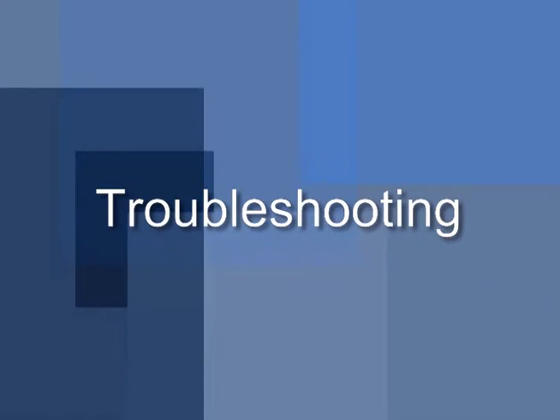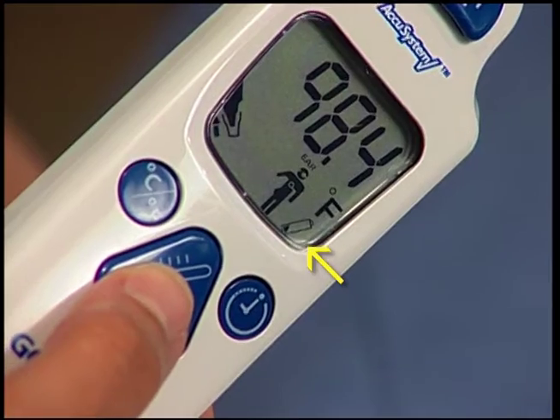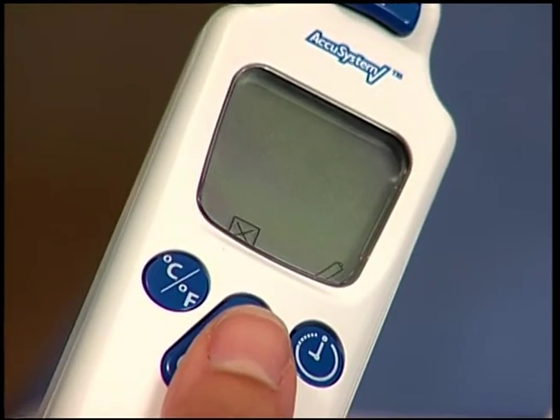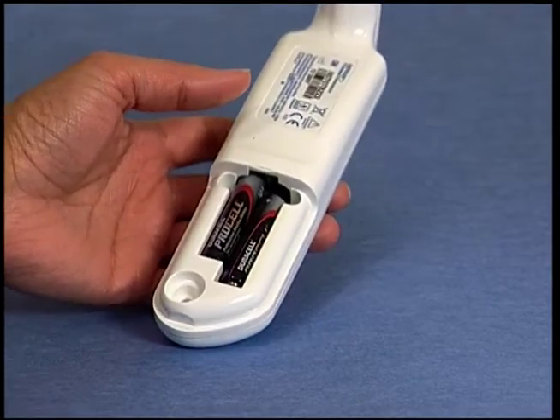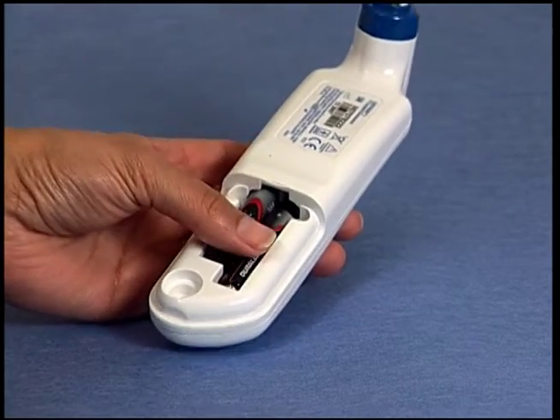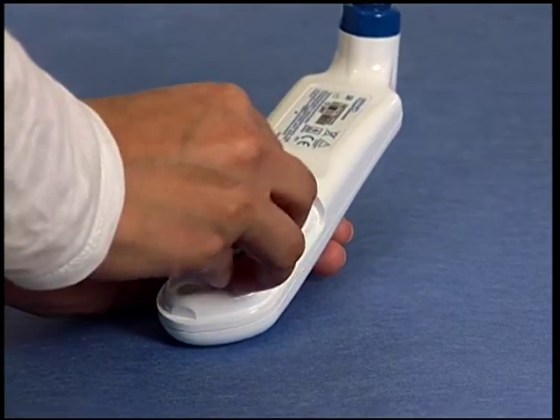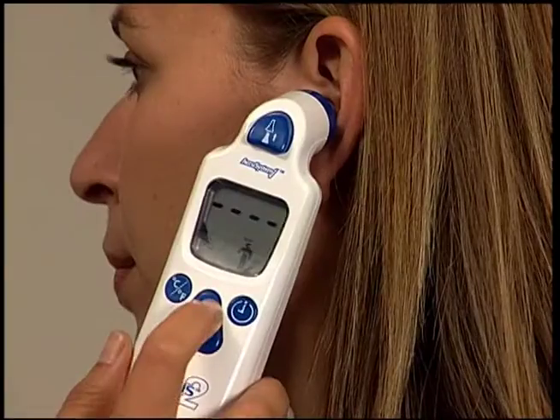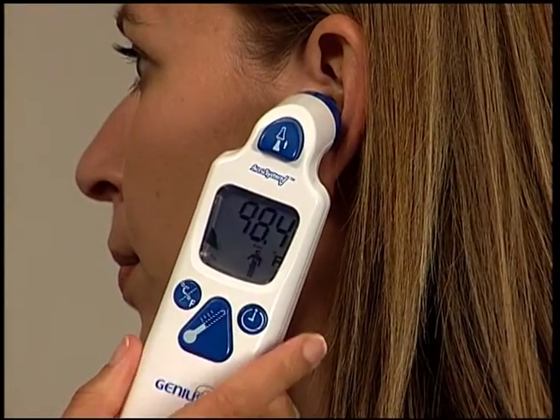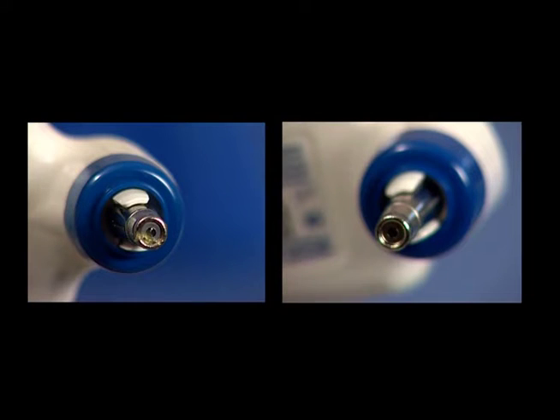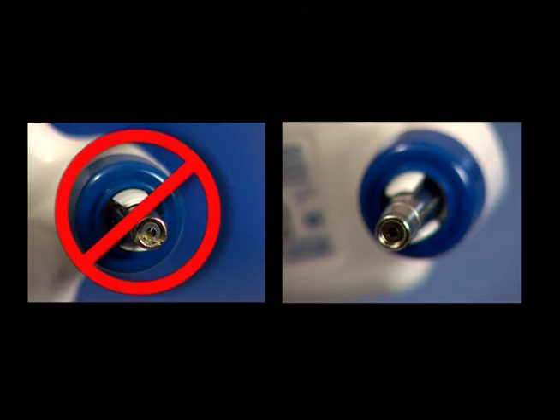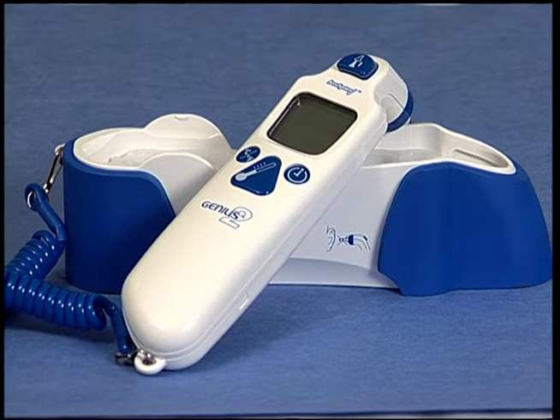Troubleshooting. If the low battery prompt or dead battery prompt appear on the Genius 2 LCD display, you should install 3 new AAA batteries, following the simple instructions in the Genius 2 operation manual. It is important to keep your Genius 2 clean. Accurate temperatures depend upon a clean, unobstructed lens. Always inspect the lens before use and confirm a clean, shiny surface free of any fingerprints or debris. Regular lens cleaning is recommended for optimal performance.